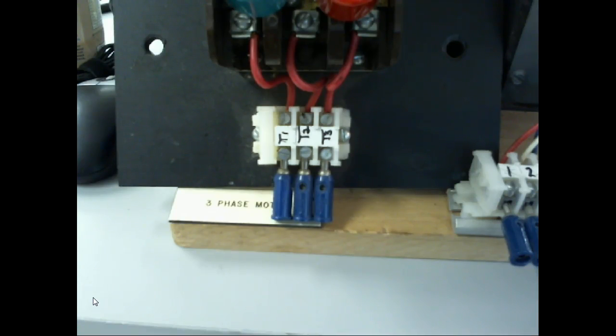Since the motor will be single phasing, the motor may not start. You may have to do what? Give the shaft of the motor a turn, because we don't have a start winding in this thing. So we have to have a phase shift, right? You understand? So what we did is we just started single phasing the motor without a start winding. And it's just going to sit there and hum. So you might have to do what? Just spin the shaft a little bit. If you don't, it's going to kick your overload out.